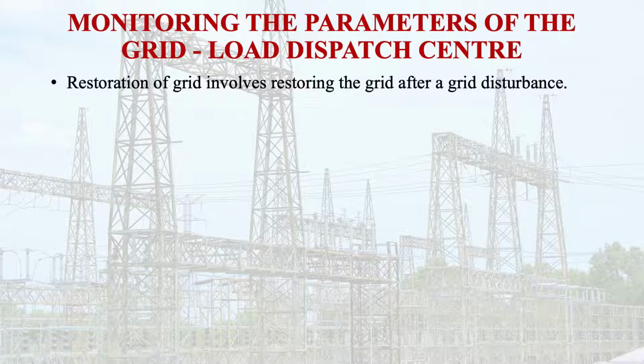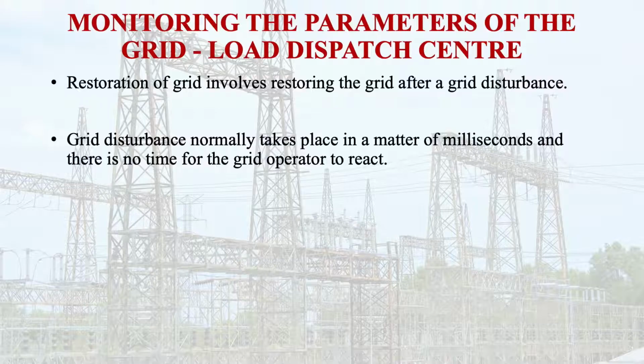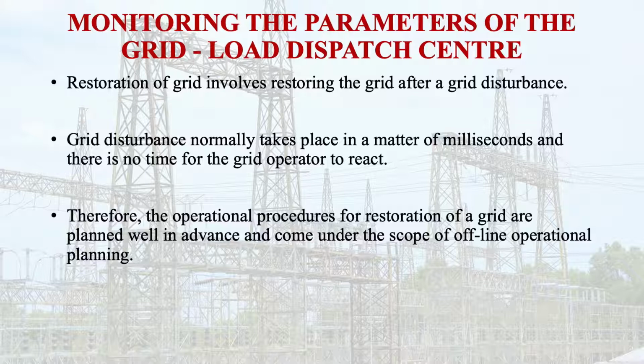Sometimes restoration of the grid is also required. Restoration of the grid involves restoring the grid after grid disturbances. Once a grid disturbance occurs, it is necessary to restore the grid. A grid disturbance normally takes place in a matter of milliseconds, and there is no time for the grid operator to react. Therefore, the operational procedures for restoration of the grid are planned well in advance, and these come under the scope of offline operational planning. So the grid operator just has to follow the procedure for restoring the grid.